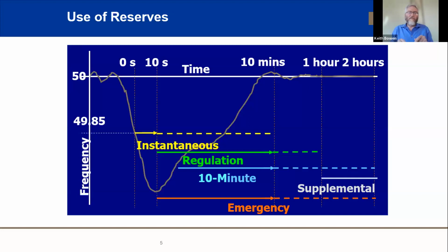So the idea is you certify a whole lot of generators to be able to provide that capability. So it might be 40 to 50 megawatts per generator, and you want 500 or 600 megawatts. So you're trying to get 10 or 12 generators provided. The other benefit of that is that it gives you more movement, faster movement. Because each generator has a ramp, if you send a signal to 10 generators, you get 10 times the ramp effectively. So you're able to move up and down a little bit faster on the regulating reserve.